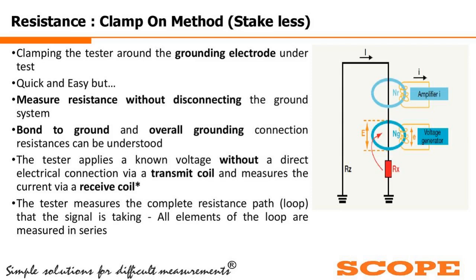However, before going into those buts, or the limitations of this method, let us talk about how to measure resistance without disconnecting, and what the benefits of the process are. We can measure the resistance without disconnecting the ground system, so no disconnection of the grounding system or earth wire is required. Bond to the ground and overall grounding connection resistance can be understood easily. It is bonding to the ground: how good is the bonding? The better the bonding, the better the leakage current flow will be. So it is giving the indication of the bonding to the ground and overall grounding connection resistance.